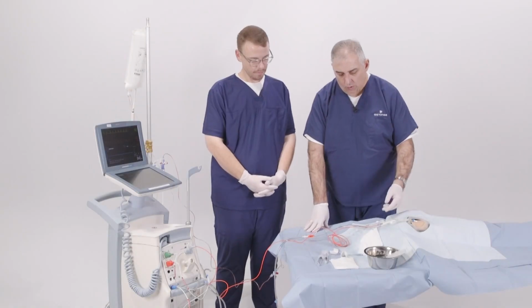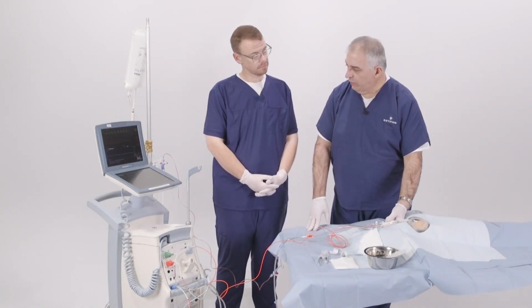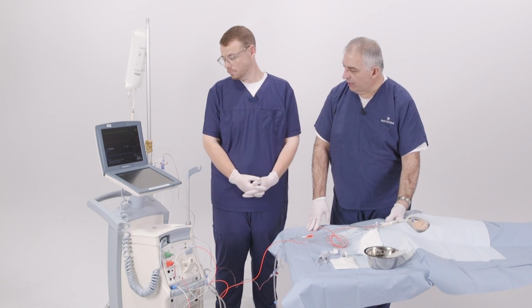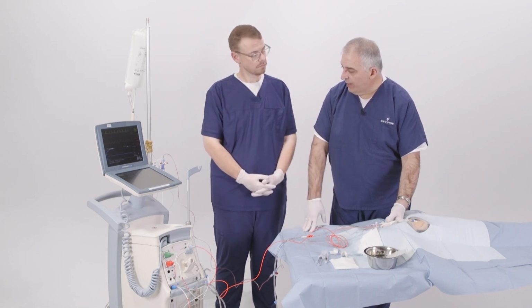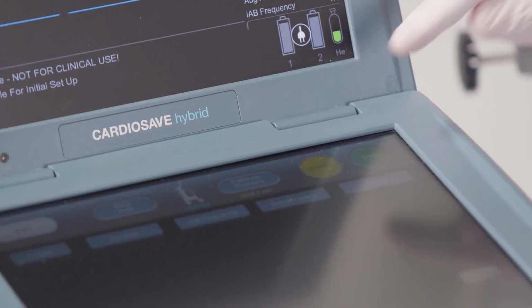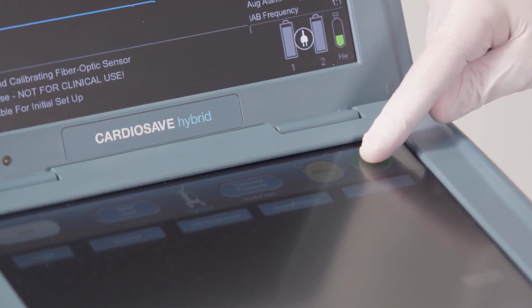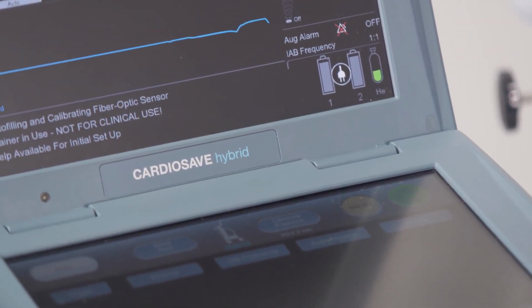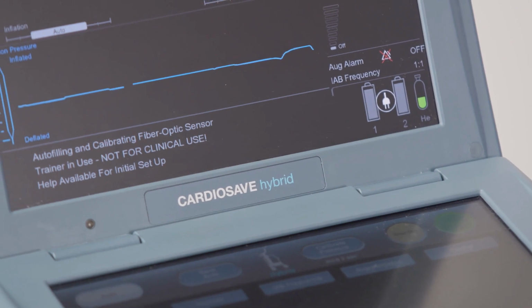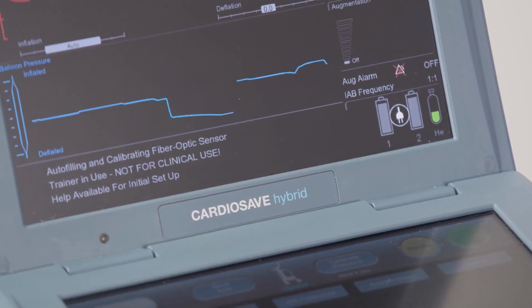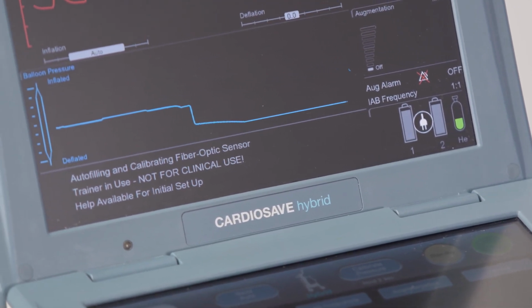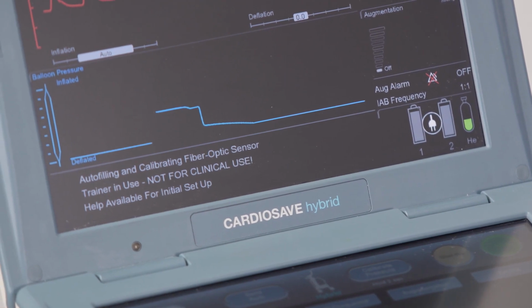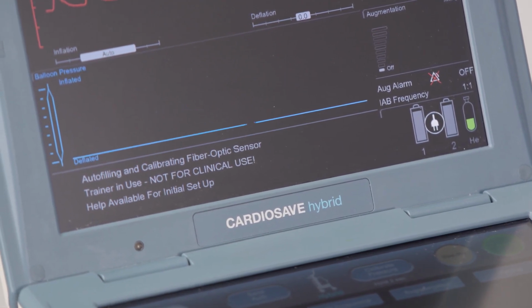All right, Prentice, now that we're all hooked up, we're going to need to press the start button to initiate therapy. The green button in the upper right-hand corner of the touchscreen, if you could press that for me, please. Excellent. It will take a few seconds now for the balloon pump to autofill and calibrate the fiber optic sensor. This is a great time to point out that at all times the CardioSave should be plugged into AC power.